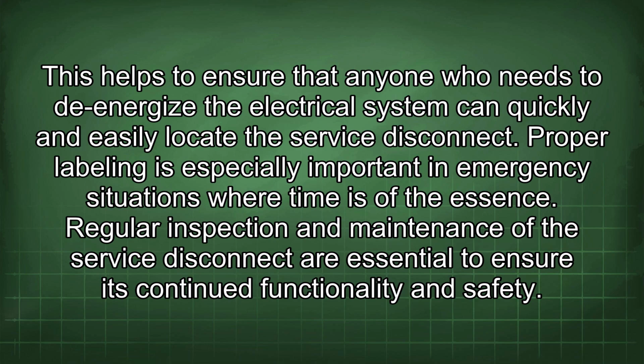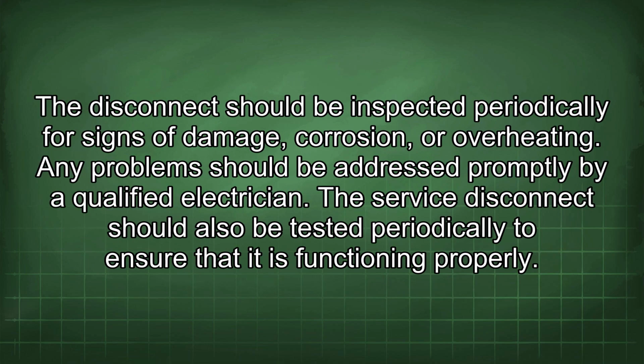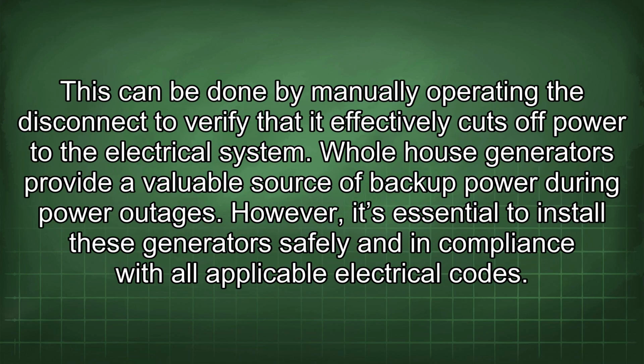Regular inspection and maintenance of the service disconnect are essential to ensure its continued functionality and safety. The disconnect should be inspected periodically for signs of damage, corrosion, or overheating. Any problems should be addressed promptly by a qualified electrician. The service disconnect should also be tested periodically to ensure that it is functioning properly. This can be done by manually operating the disconnect to verify that it effectively cuts off power to the electrical system.